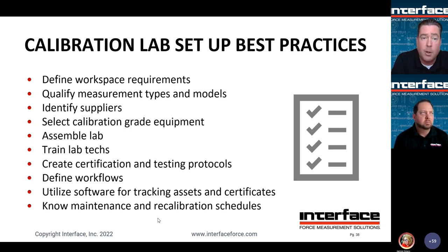At Interface, and I know other folks on here have different software that is used for tracking assets and certificates. That really helps workflow, making sure that things are flowing through to different databases. For example, pulling calibration data into a database and generating certificates and trying to avoid any manual type of calculations being needed. And then, of course, knowing your maintenance and recalibration schedules. When are your standards due for calibration? Do you have a second standard that's on a rotation to make sure you're minimizing downtime for said standard? What kind of PM is required for your cables, your adapters, the load frames, making sure if you're using hydraulic, for example, making sure that those are on a regular PM schedule to avoid unscheduled downtime. Next slide, please.